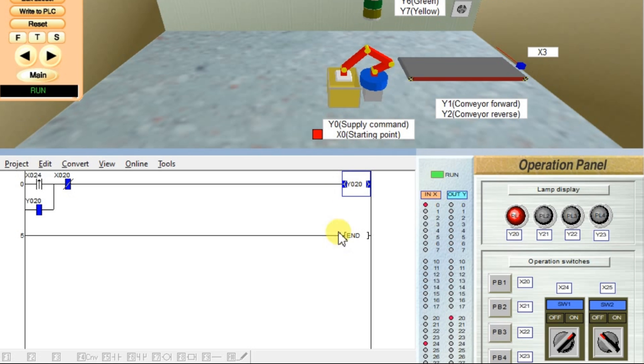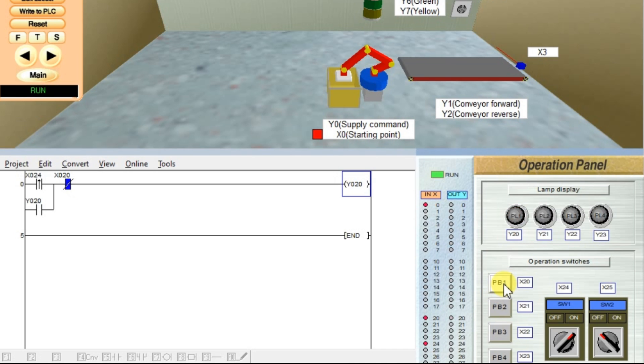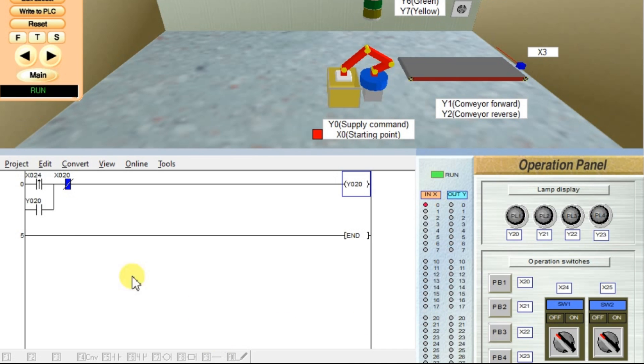Previously also, the output Y20 is turned on, but the time duration is in milliseconds, so we are unable to see it visually. You can unlatch it by pressing X20 or push button 1. Now input X24 is in ON state. I will change the state from ON to OFF. Click on it. Nothing happens because this is the rising edge. It will only work when input changes from 0 to 1.